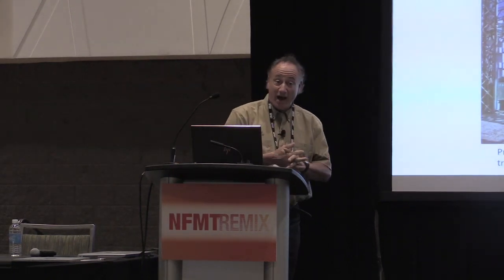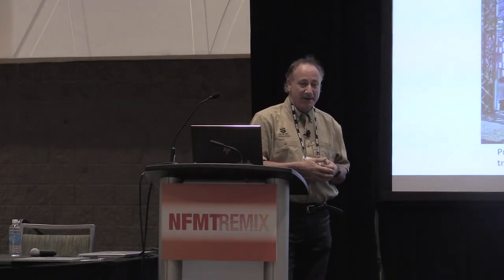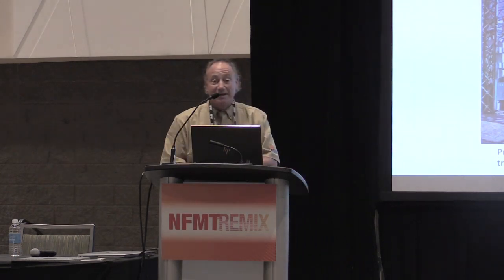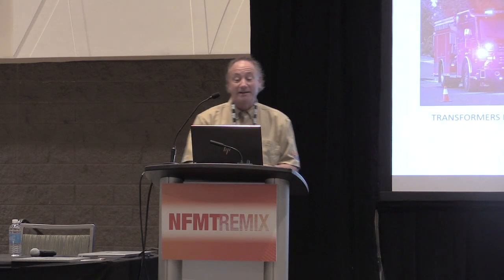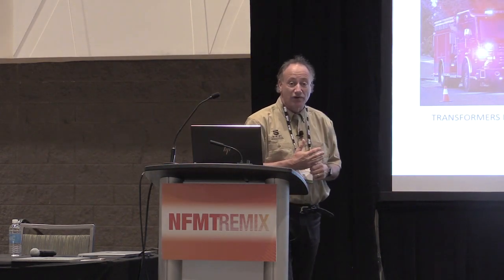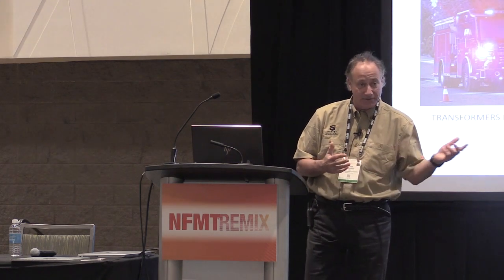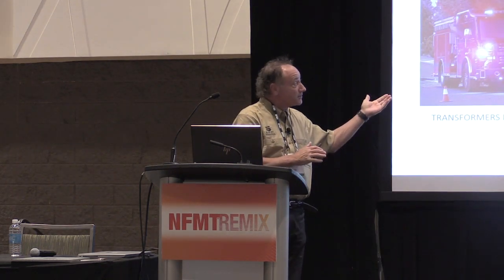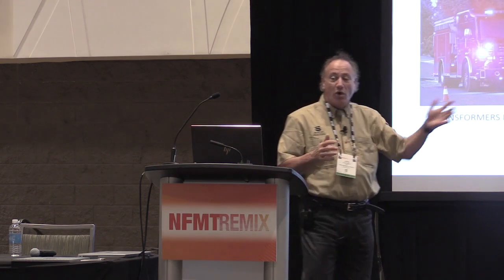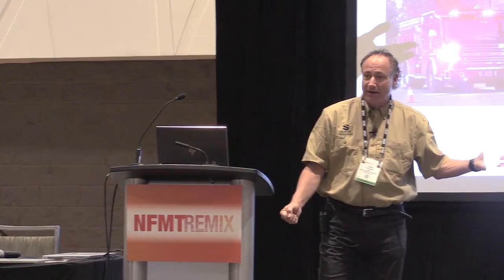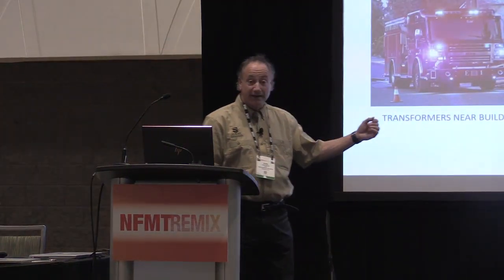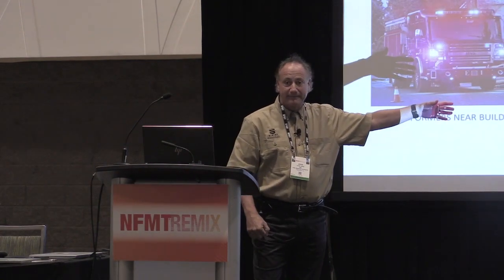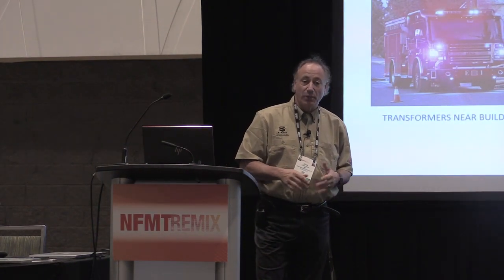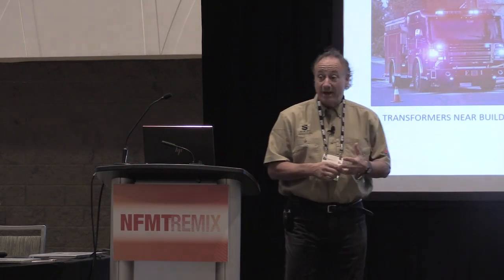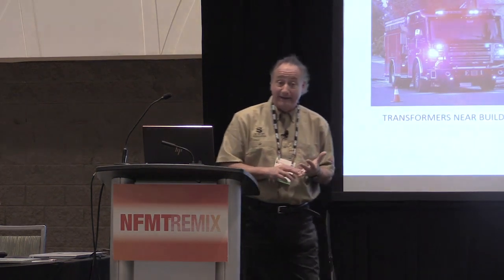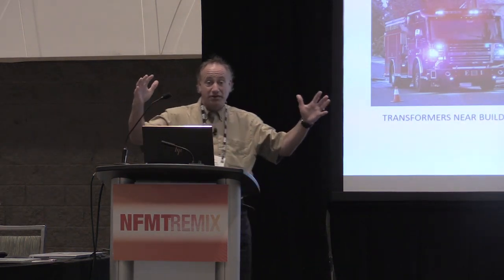Some of them are occupied, some of them are not. We started way back in the day protecting people, and now we're protecting things like energy storage, emergency systems, and we're doing it typically through providing protection to the large transformers and substations that provide power to the facility. So you'll find transformers, when they fail, you could walk up to a transformer with a match and you're not going to light it up. Right? When it fails internally, it fails with an explosion. That explosion throws shrapnel, ball bearings, ceramics, up to about 250 feet with the force of a .44 Magnum. It's measurable. It's an implosion and then a force.